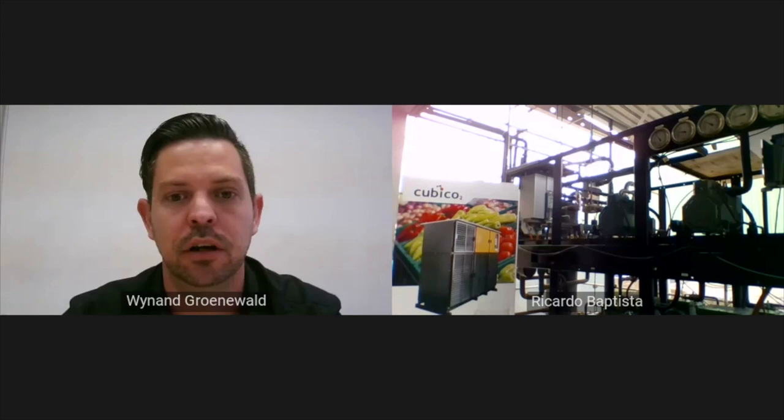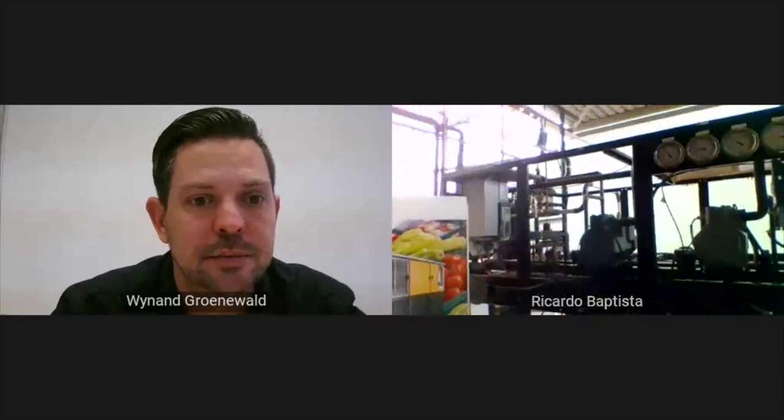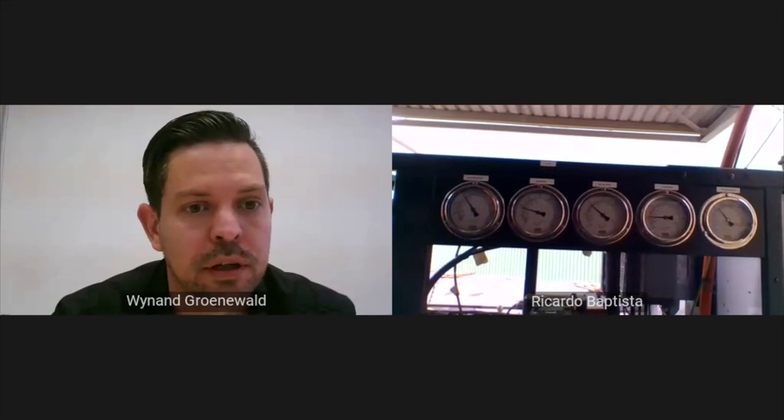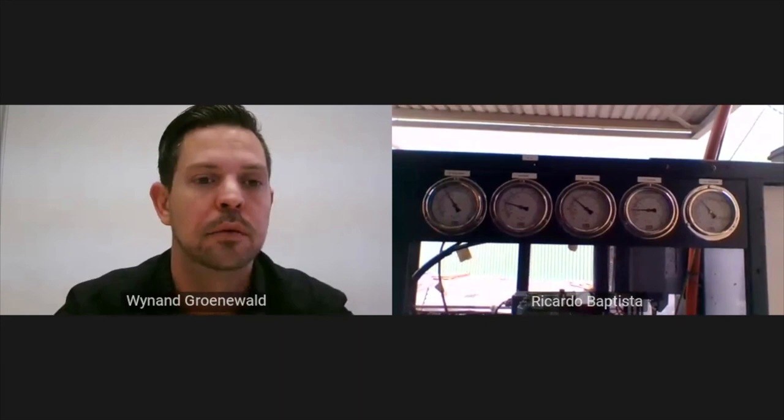Looking at the gauges, with a cool ambient today the system is running in subcritical mode at about 63 to 64 bar — a nice subcritical operation. Medium temperature and low temperature suctions are at their respective pressures to maintain cooling, and receiver pressure is set at about 38 bar. So the high pressure valve is reducing pressure from 65 bar discharge down to 38 bar receiver pressure.